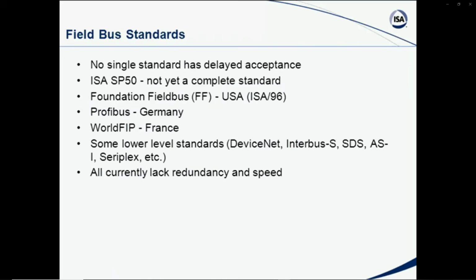This is just an indication of what I mentioned earlier: there were milliamp wars and there were pneumatic wars, and fieldbus wars also have taken place. So there's been a lot of modifications, a lot of things introduced. People are settling down to a large extent. There's maybe not a complete standard on the ISA 50 standard, but Foundation Fieldbus was introduced at ISA 96, and that's become a major player in the fieldbus war. Profibus came out of Germany, WorldFIP out of France. There are other standards being used in certain types of devices.